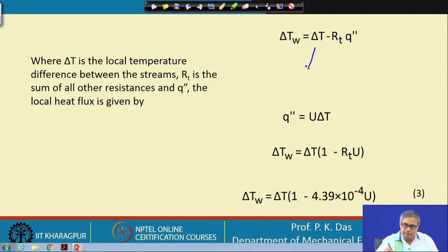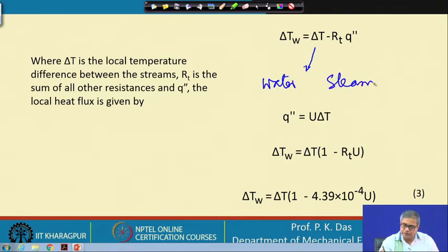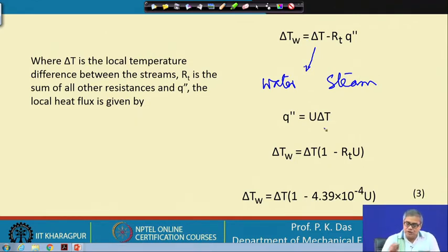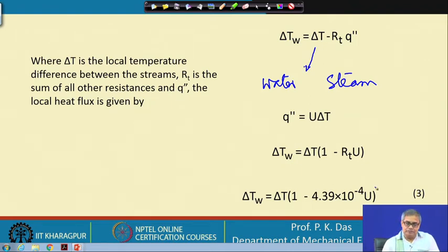This gives the temperature difference between water and steam, where delta T is the local temperature difference between the two streams, R_T is the sum of all the other resistances, and q double-prime is the local heat flux given by q equals U times delta T per unit area. Delta T_w is then obtained by this formula. Putting in all the values of R_T that we have calculated, we get this equation — equation 3 — which we use for iteration.